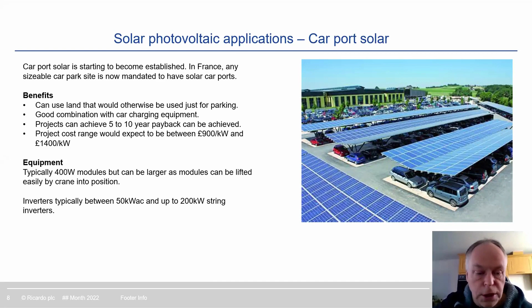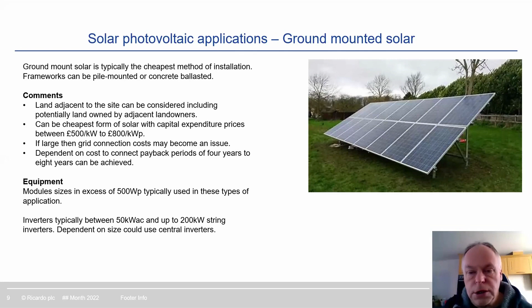Ground mount solar is typically the cheapest form of solar. These are modules on fixed frameworks typically, although many countries also use tracking systems, which is where the solar modules are moved to track the sun. Costs are likely to be between £500 per kilowatt to £800 per kilowatt, with large systems in excess of 500 kilowatts likely to trigger concern from utilities, and therefore grid studies would be required.